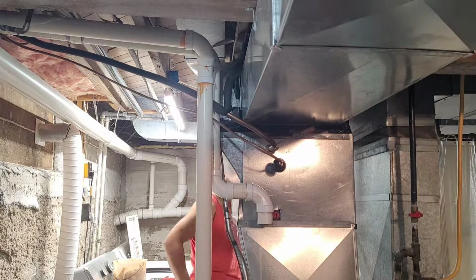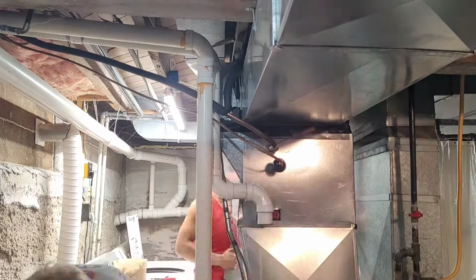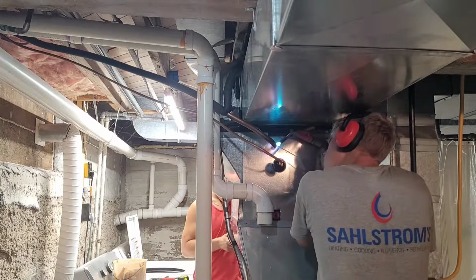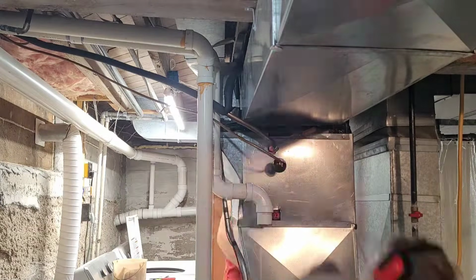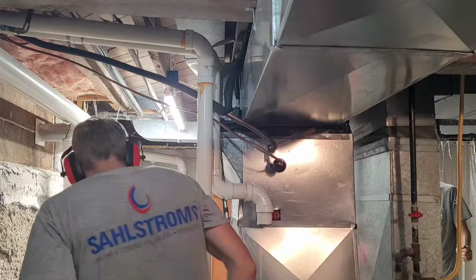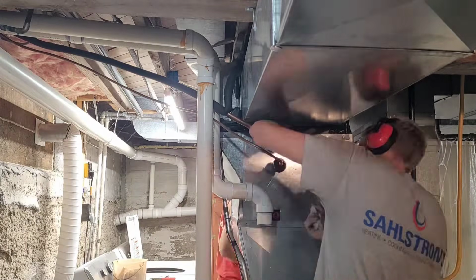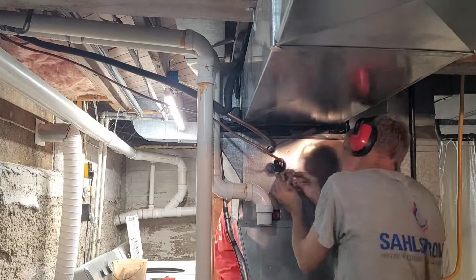Whenever we're installing an air conditioner, it is always a race to get all of the braze connections done, because we have to pull a vacuum on the system, and that actually takes a good amount of time. So you want to get the vacuum started as soon as possible and then finish buttoning everything else up while it's pulling down.